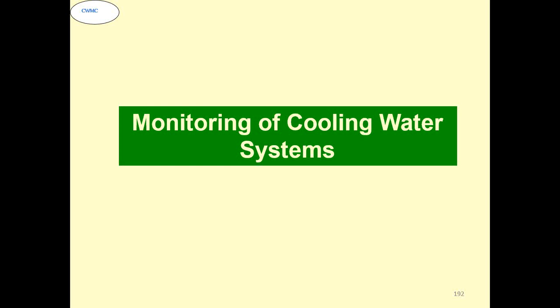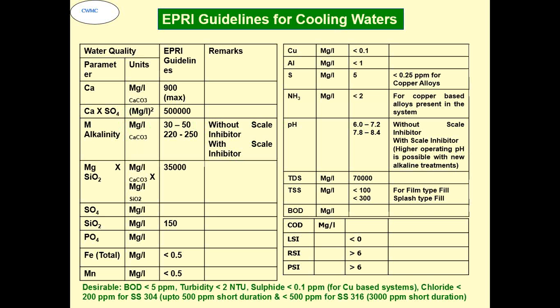Monitoring of cooling water systems. These are the typical guidelines given by EPRI, the US Electric Power Research Institute, for cooling water. If you look at it, calcium not more than 900, calcium times sulfate not more than 5 lakh, M alkalinity 30 to 50 without scale inhibitor, and 220 to 250 with a suitable one. Nowadays we can go up to a higher pH, almost up to 9 pH, with a good quality of chemicals.